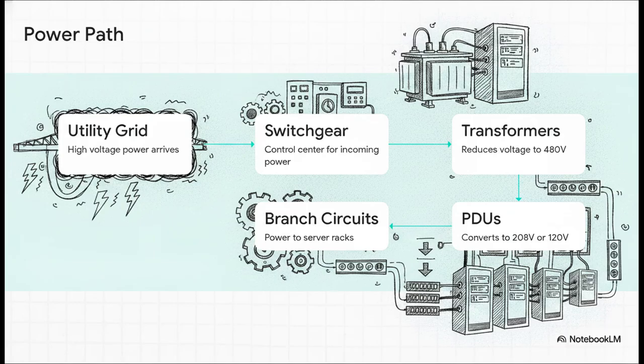To handle that massive voltage, the power path inside a data center is essentially a series of carefully controlled voltage transformations. The power steps down safely in stages: starting from the utility grid, it moves into the switchgear, then through step-down transformers, into power distribution units (PDUs), and finally flows through branch circuits and rack power strips directly into the servers.